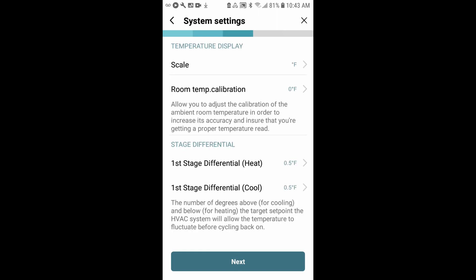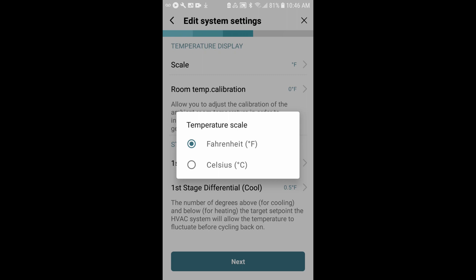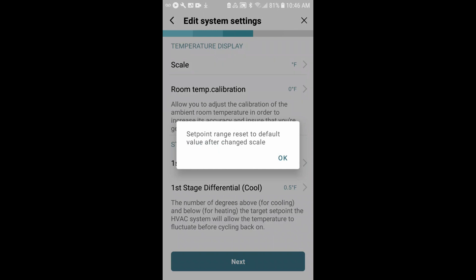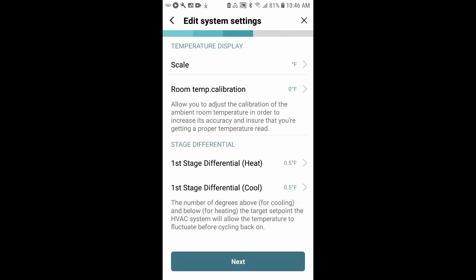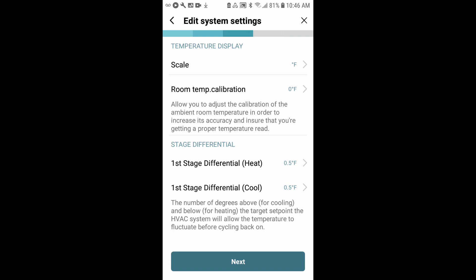Now we'll go into system settings. Within system settings, you can adjust the scale, meaning what's going to be displayed for the guest. We would like to leave it in Fahrenheit. Then room temperature calibration gives you the option to adjust in case you find that your thermostat needs to be calibrated a little bit. You can adjust that up or down a couple degrees. You really shouldn't need to mess with that. The stage differentials - this is just when the compressor or the heat's going to kick in. It's going to be within a half a degree of the target temperature. We'll tap next.